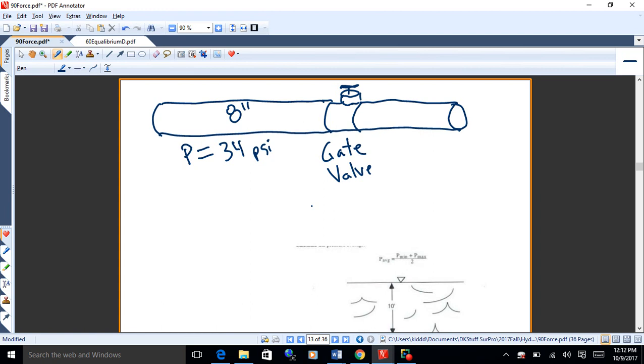So gate valves are on-off valves, right? What happens when you try and throttle flow with a gate? Yeah, it starts chattering in the seat, or wears them out. So you don't throttle with a gate valve. A gate valve is meant to shut stuff down, which is primarily what you do in a distribution system. If you want to throttle, you might have to use a butterfly.